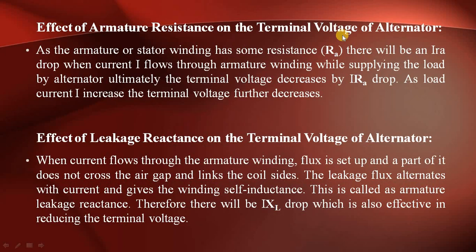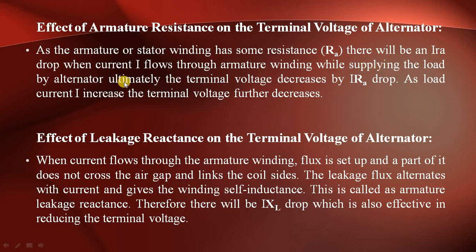Now we will see the effect of armature resistance on the terminal voltage of the alternator. The armature or stator winding has some resistance. After supplying load, the terminal voltage is reduced. When load current flows through the armature winding resistance, there is an IRA drop, and the terminal voltage decreases. If load current increases, the terminal voltage will decrease further.